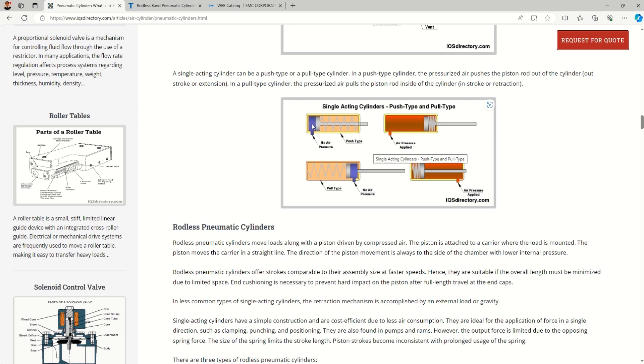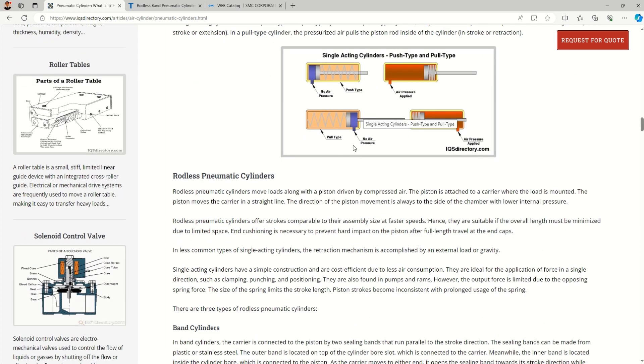In a pull type cylinder, the spring is on the piston side, and at the home position the piston rod is at the extended position due to spring force. The rod remains extended unless air is supplied. When we want retraction, we pass air on the piston rod side, which forces the piston rod against the spring force to give the retracted stroke. So in pull type, the cylinder is always at the extended position by default.